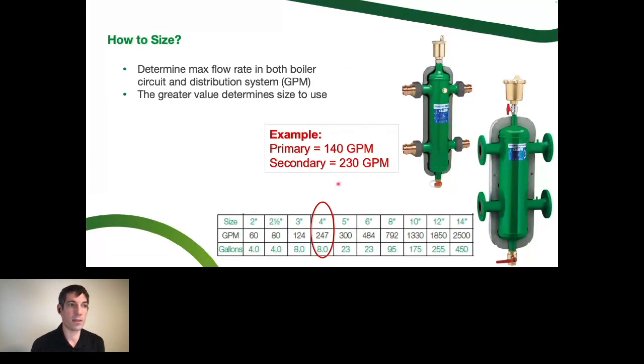So we've got a different delta T in that scenario. So we just pick the bigger number, just one of those numbers. We don't have to combine these or anything. We don't have to add them together. So in this case, to cover the biggest number there, a 247 is going to be a good fit. So a 4-inch separator.